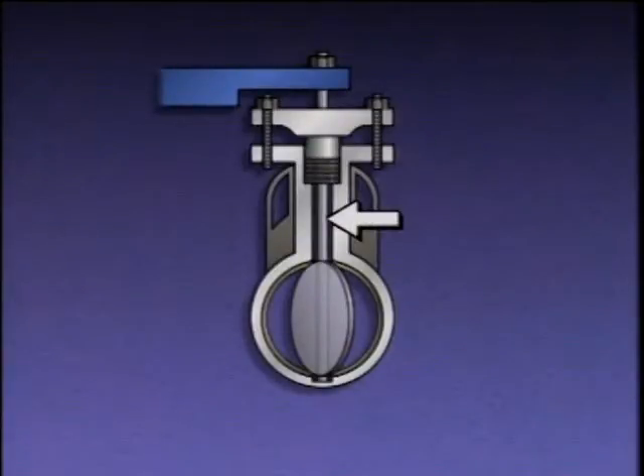The disc is attached to the stem, which rotates the disc when the handle is moved, and the flow rate is adjusted by changing the angle of the disc. The butterfly valve requires only a 90-degree, one-quarter turn of the handle to go from fully open to fully closed. When the handle is in line with the valve's inlet and outlet, the valve is fully open; when perpendicular to the piping, the valve is fully closed.